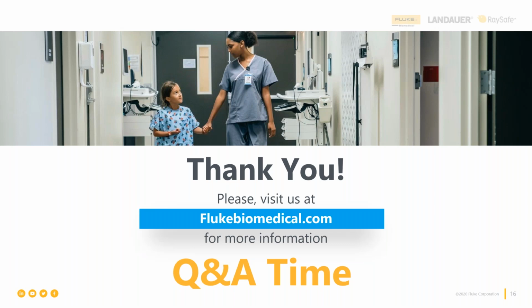Okay. Another question here is that we have a doctor who's complaining about the accuracy of the device. How can I prove to him that the device is accurate? Okay, if you're sure that it's accurate, in other words, you have taken his complaint at face value and you've done a static pressure comparison to make sure that device is accurate and you're confident that it is, then the next thing is to invite that doctor to listen on the limb that the cuff is placed on while the oscillometric or automated device makes its determination, makes the measurement.